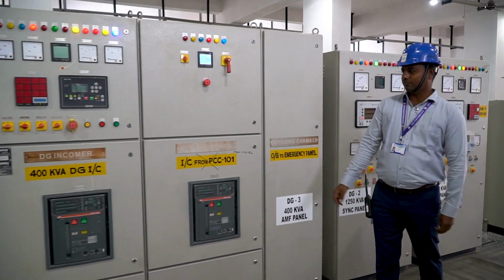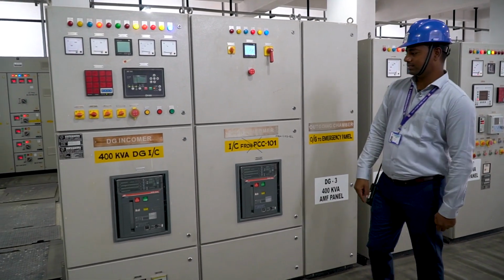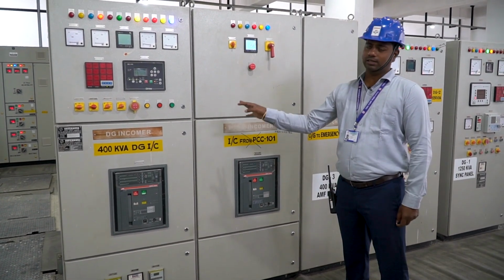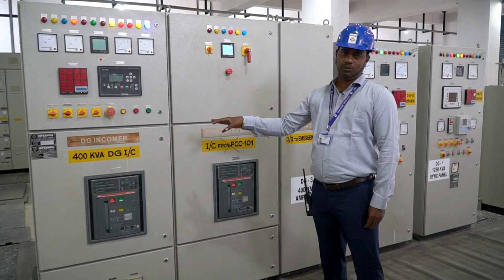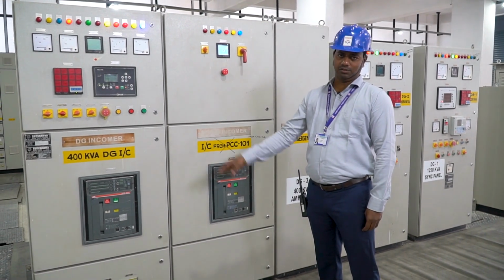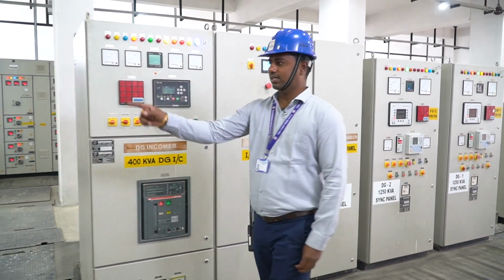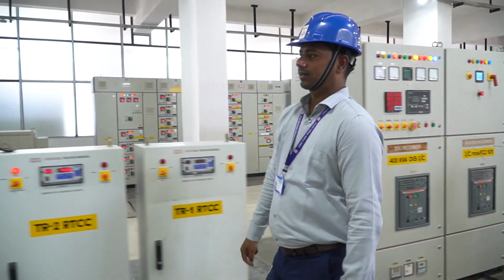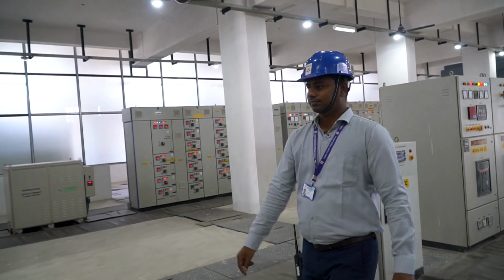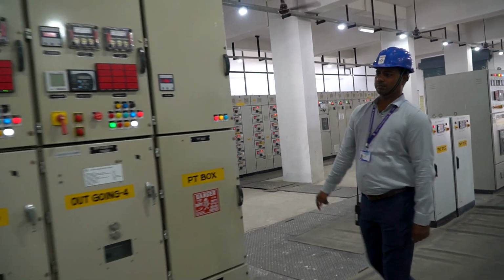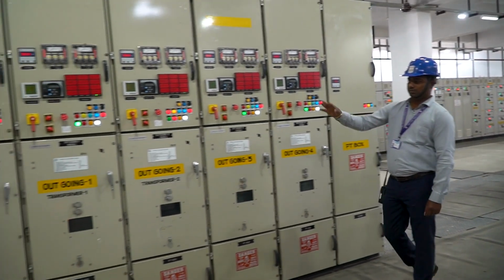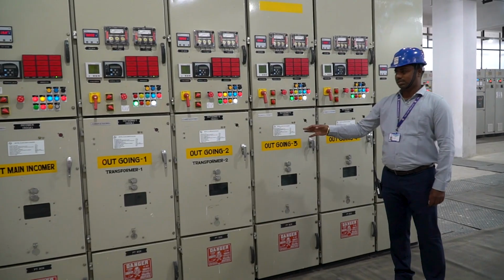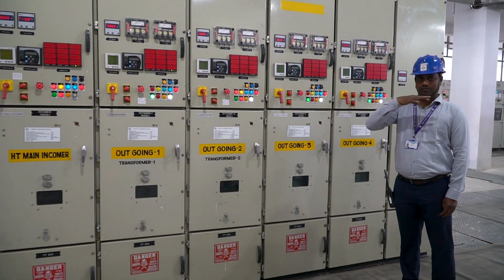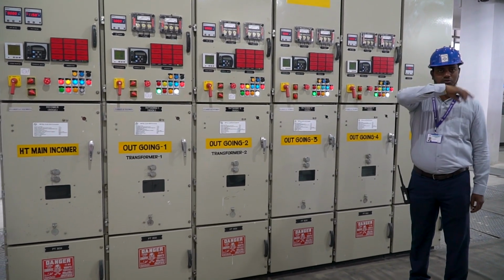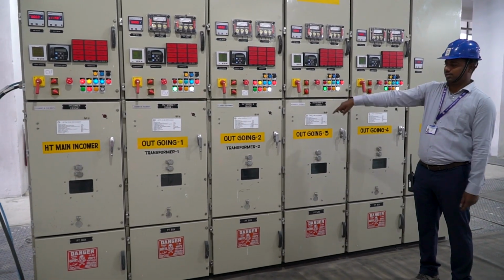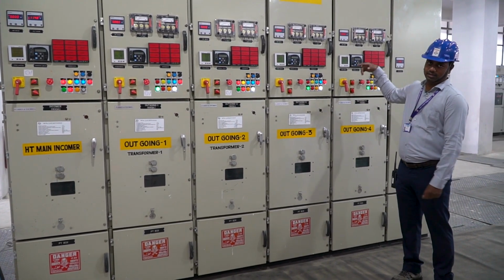Here, for the 400 kVA DG, a separate DG incomer is available. This will deliver the desired current only to the emergency panel connected loads. And that is our HT incomer. We have two sets of HT incomer from two transformers, transformer 1 and transformer 2. Presently transformer 2 is live, and from transformer 2 the power comes through the incoming panel to here. From here it gets distributed.